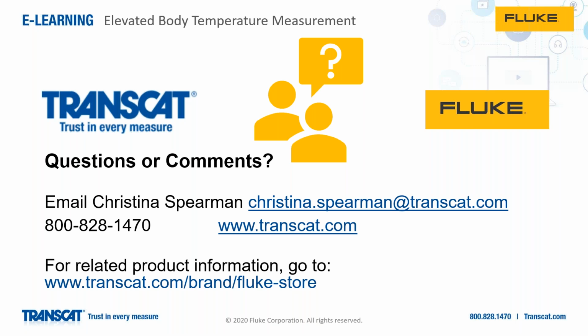The next question: do these products need to be calibrated, and if so, how long is the calibration interval? Yes, any product offering these kinds of accuracies that comply with the FDA's enforcement policy will need to be calibrated. For the 67 Max, the calibration interval is 1 year, during which the product is guaranteed to stay within its stated specifications. After that year, it's just a recommended calibration cycle — we can't dictate when people have to come in, but specifications are guaranteed for that 1 year span without further calibration.